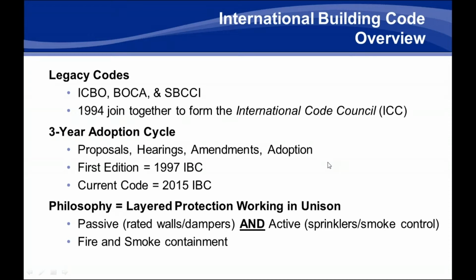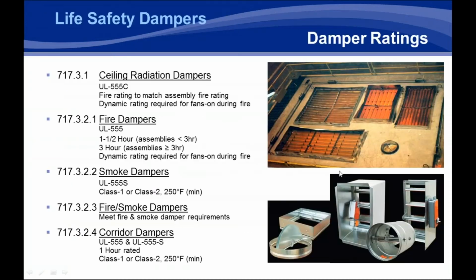And the code works basically to add layered protection, which would be both passive and active, where your passive protection comes from rated walls, rated assemblies, and dampers, while your active protection comes from both sprinklers and, say, smoke control type systems, typically under 909 section of the building code, and we will talk about that later. And basically the layered protection works for fire and smoke containment.